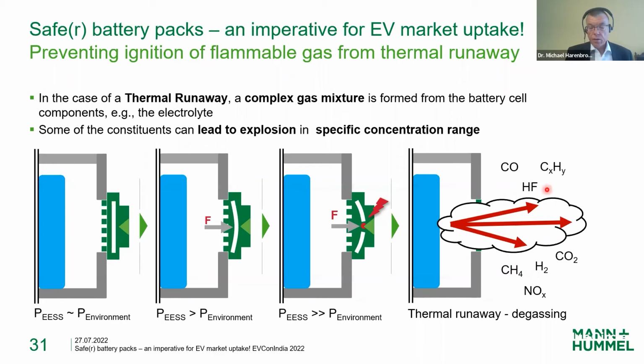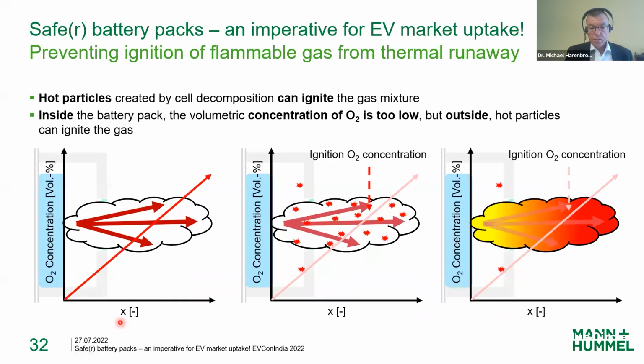Here, outside of the battery pack, those gases start to mix with the ambient air, and thus the concentration of oxygen is also increasing. And so now what's happening is we have a mixture of flammable gas and oxygen just in the right concentration range, so it can be ignited.